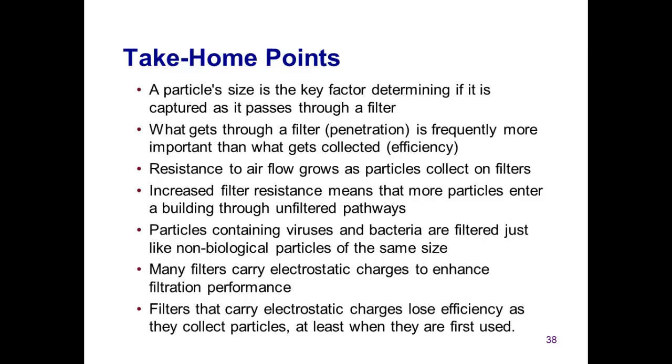It's important to keep in mind that particles containing viruses and bacteria are filtered just like non-biological particles of the same size. Some filters utilize fibers carrying electrostatic charge to enhance their performance. However, filters that carry electrostatic charges lose efficiency as they collect particles. That change in efficiency does not necessarily mean that electric filters should not be used, because they can have important advantages in pressure drop and efficiency. However, users should consider their filters and potential changes in performance over time in the context of their entire system. The performance of filtration systems in swine operations over time is an area that we need to study more.